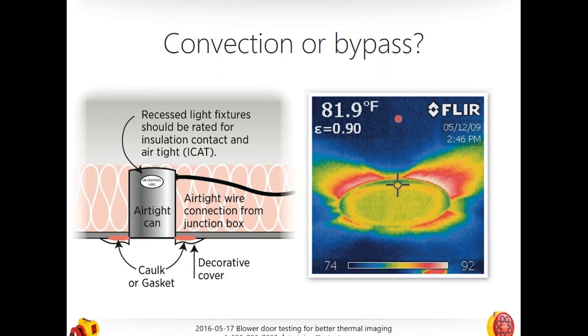Here's a perfect schematic example showing an airtight recessed light can — how it should be sealed with gaskets, a decorative cover over the caulk, and airtight wiring. But this is what happens when it's not sealed. In a cool home, this light penetrates through the ceiling into an attic. By depressurizing the home, we're sucking warm air in from the attic and we can see exactly where it is. That's a bypass.